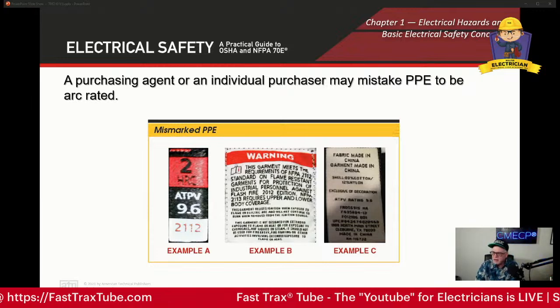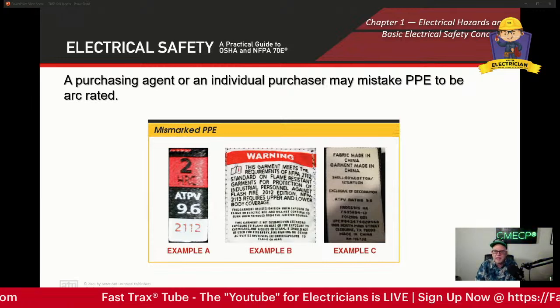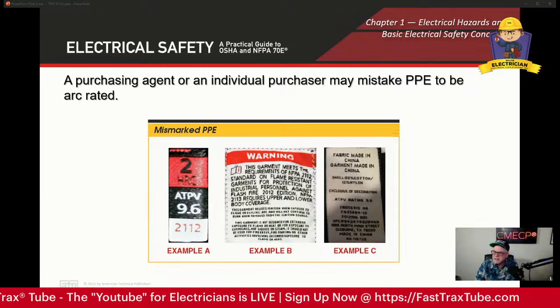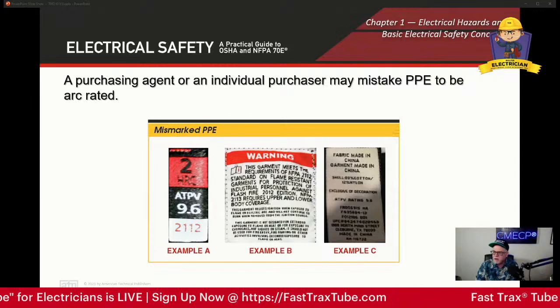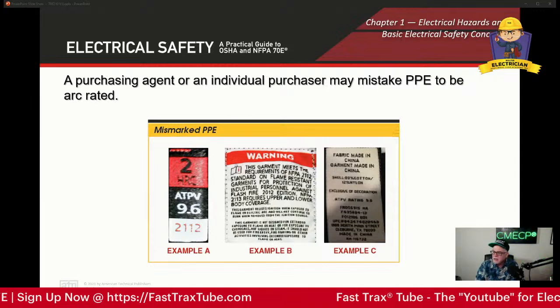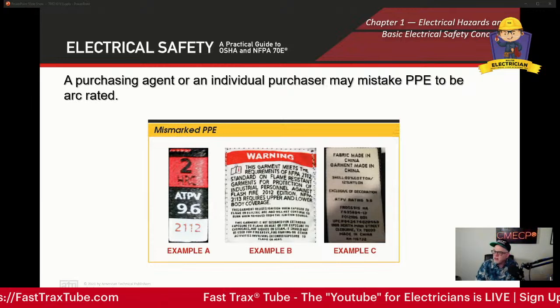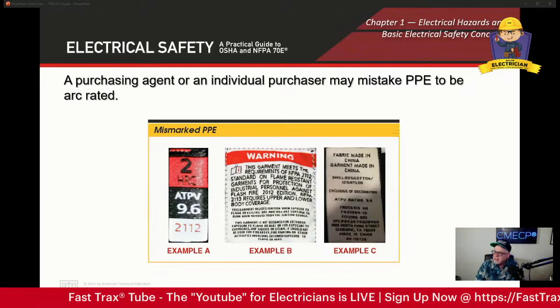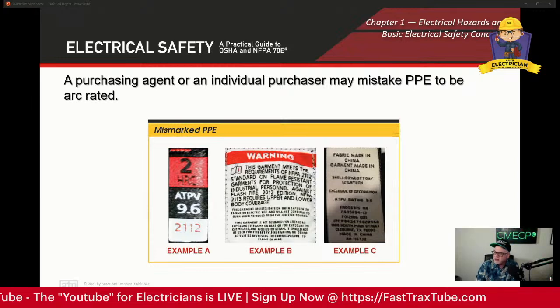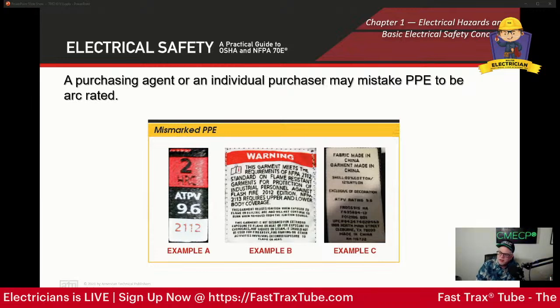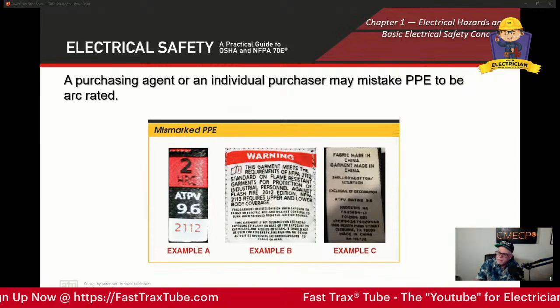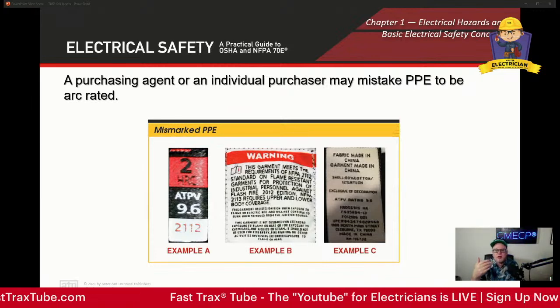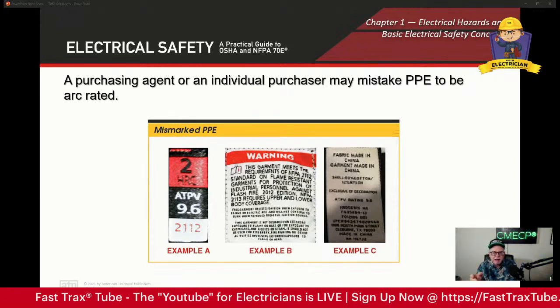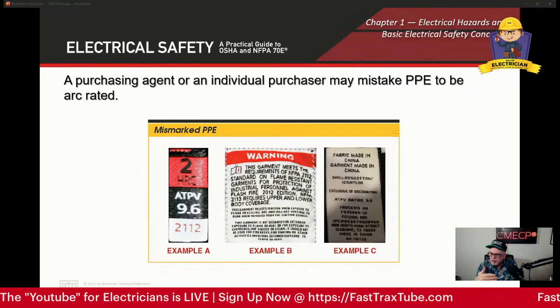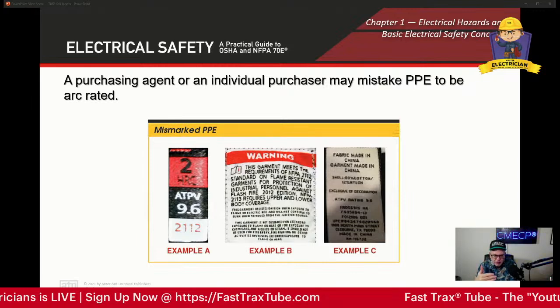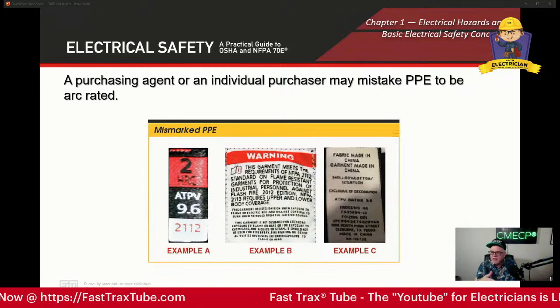If we're using NFPA 70E and some of its requirements, this piece of equipment doesn't say anything about that on it. It's just making reference to 2112. Now, if you look at example A, it shows an ATPV, 9.6, though it's hard to see, but it has no documentation to support it. So you bought it, but there's nothing to support it. Most equipment you'll buy with the PPE rating on it will have the proper ratings and give you the standard document that it's based on.